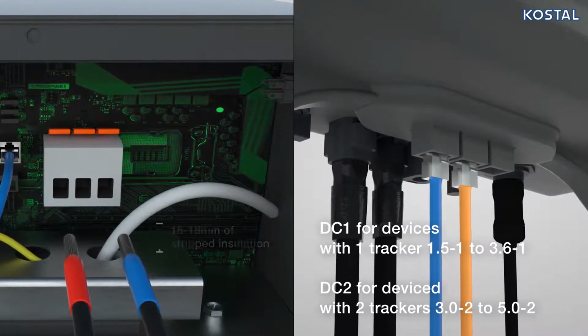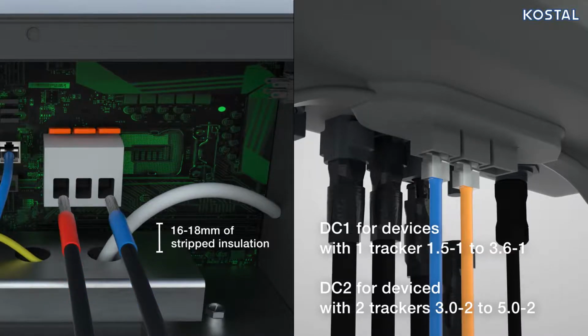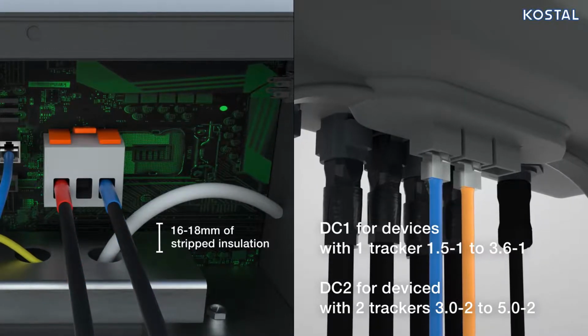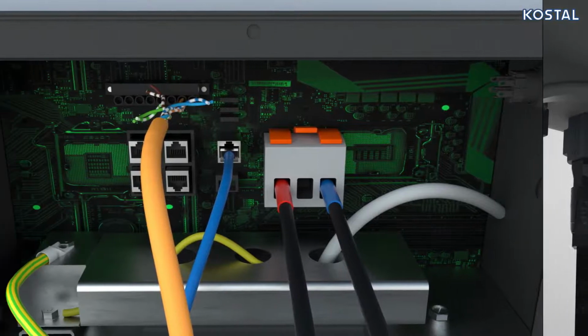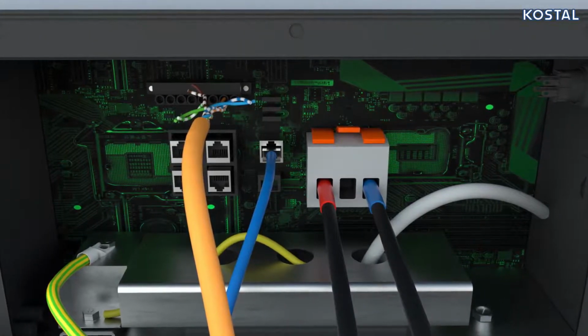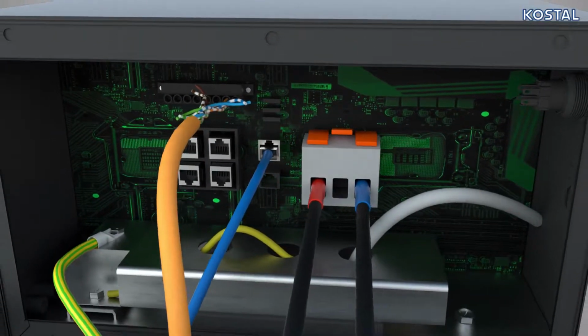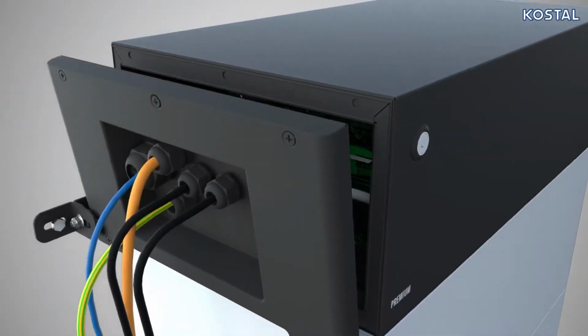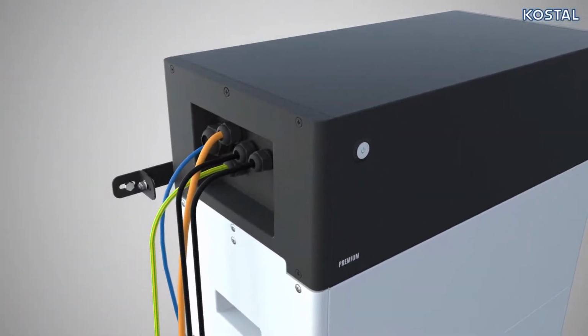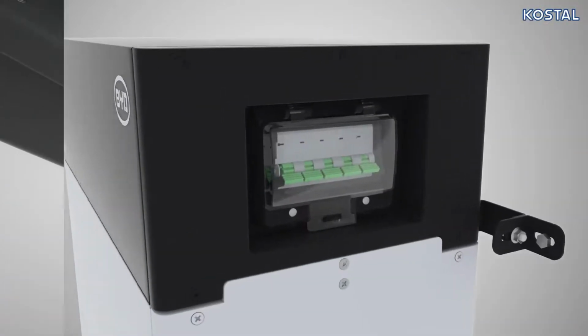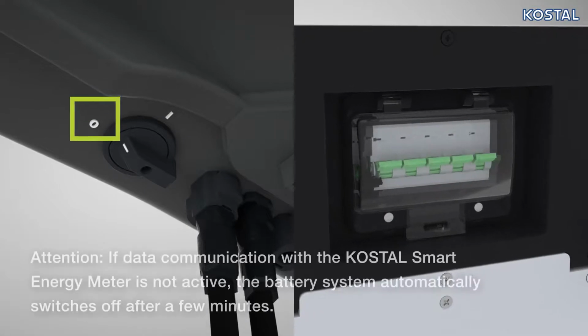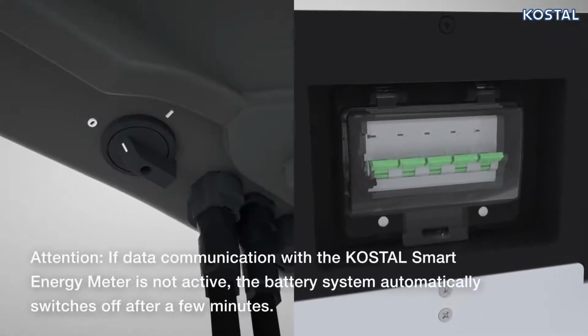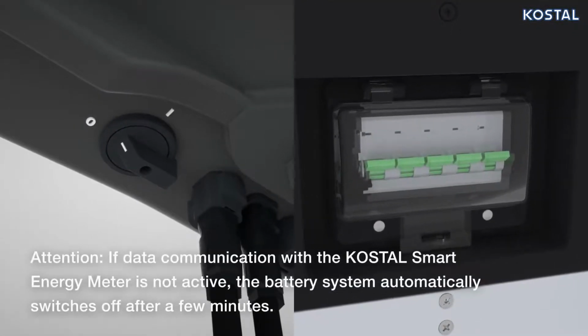Now establish the DC connections. To connect the PIKO MP Plus, please use the pair of SUNCLIX plugs provided. Now install the cover of the terminal compartment and tighten the cable glands. The system is now ready for commissioning. First, switch on the battery system by using the fuses on the right-hand side of the housing. The system starts the initialization process.